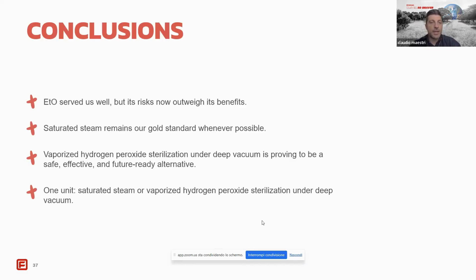So vaporized hydrogen peroxide under deep vacuum is a reliable solution for complex and sensitive types of items, ensuring both microbiological effectiveness and material compatibility, offering an alternative solution to ethylene oxide sterilization. With its flexible process parameters like number of pulses, H2O2 amount, deep vacuum target, holding time, etc., the deep vacuum H2O2 autoclave allows adaptation to ensure process effectiveness and optimization of the H2O2 sterilization cycle. So I finish my part. We are here available for any question about it.